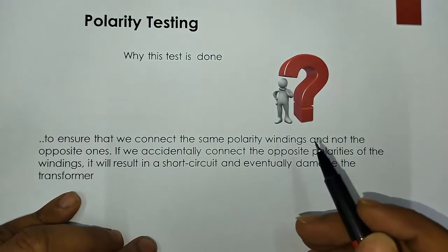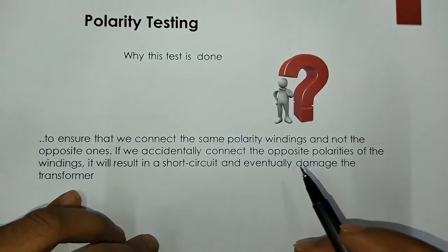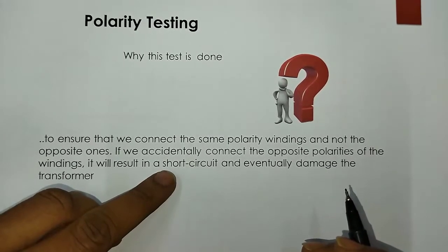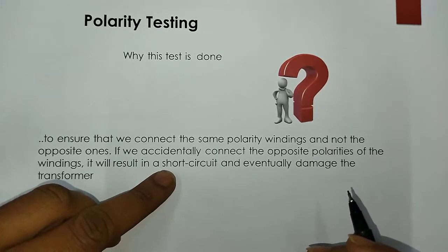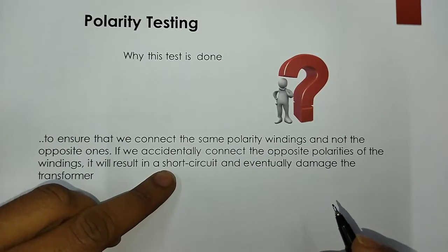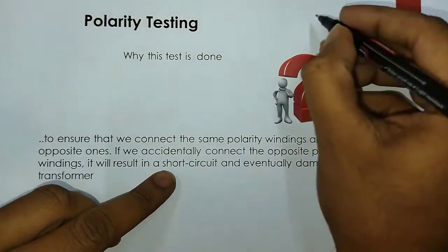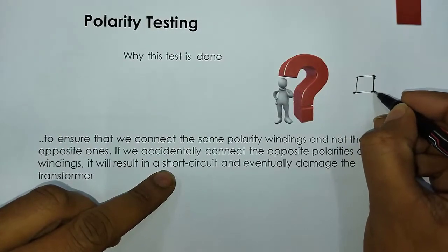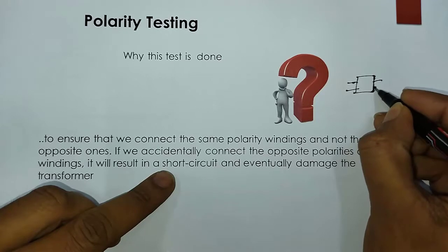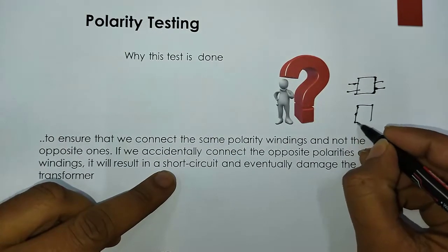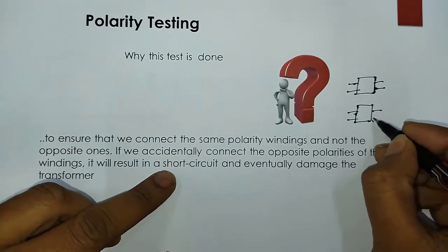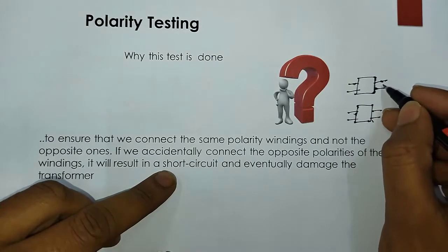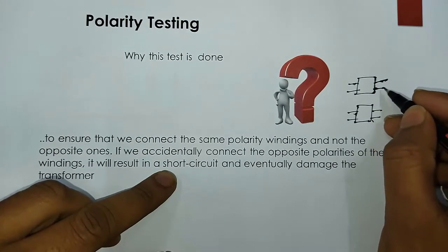First of all, what is polarity testing and why is it so important to test a transformer? Whenever you need to connect a transformer to another transformer, you have to identify the correct polarity of the transformer. Suppose there is a transformer and the load is increased, so you have to connect another transformer with it in parallel. Then you have to connect these two transformers in parallel in such a way that in the output, current doesn't circulate in a short circuit way.